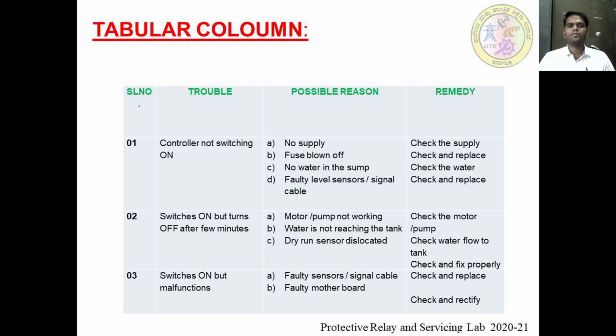The reason is a faulty sensor or signal cable, or it might be due to a faulty motherboard. Because of a fault in the motherboard or in the sensors, the signals are not coming properly, or the motherboard is not operating the signals properly. For this, check the sensors. If the fault is in the sensor, replace the sensor. If it is a fault in the motherboard, or any mislocation of an electronic device in the motherboard, then properly solder it, check it, and rectify.